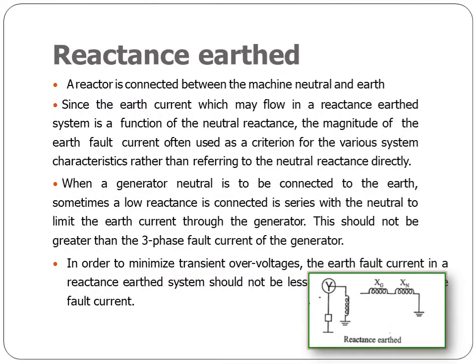Third one is reactance earthing. A reactor is connected between the machine neutral and earth. Since the earth current which may flow in a reactance earthed system is a function of neutral reactance, the magnitude of the earth fault current is often used to describe system characteristics rather than referring to the neutral reactance directly. When a generator neutral is connected to the earth, sometimes a low reactance is connected in series with the neutral to limit the earth current through the generator.